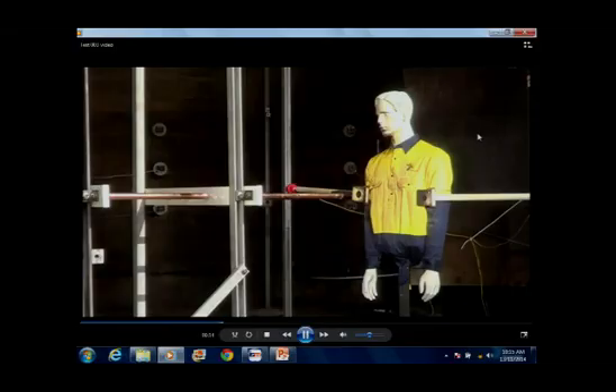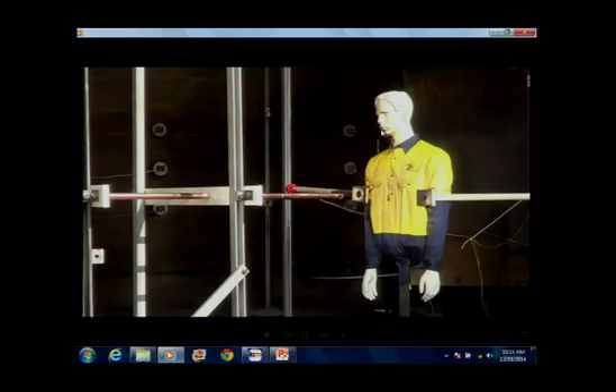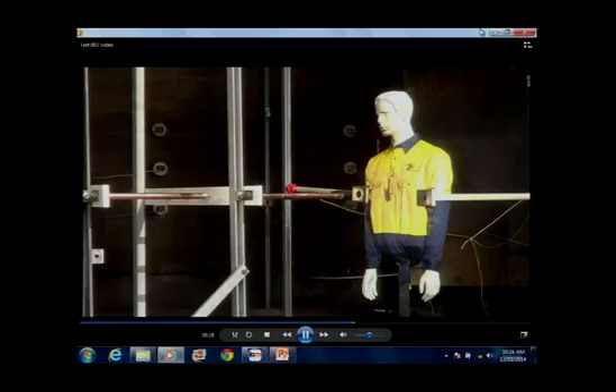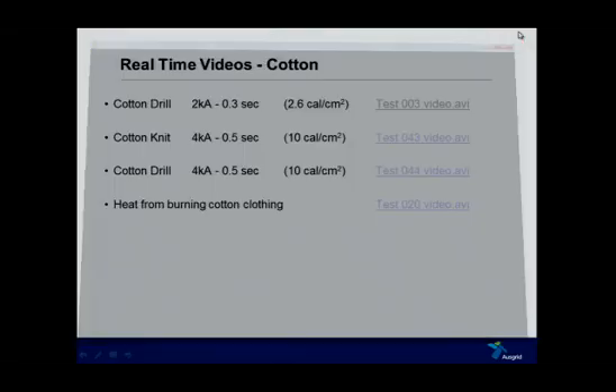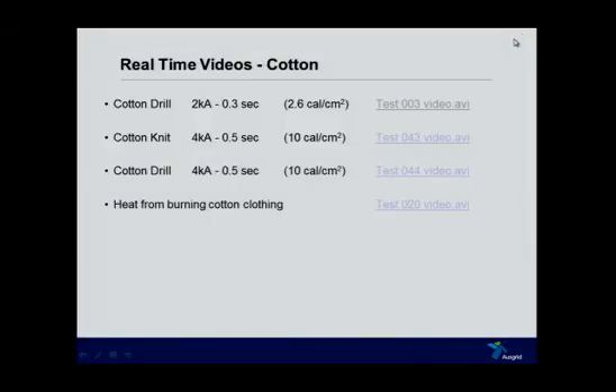So you can see, although the shirt appears to have survived, the mannequin has received burns to the face, and that's been the case in 3/4 of Ausgrid's historical arc flash injuries. It's been burns to the face, the most commonly burnt part of the body. But note that the shirt has now ignited in the centre of the chest and is continuing to burn. That's the problem with cotton, it keeps burning. With a small ignition like that, it probably would be easy to pat out.